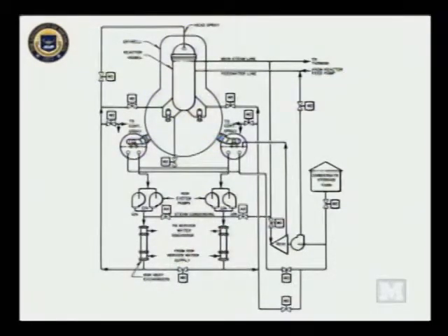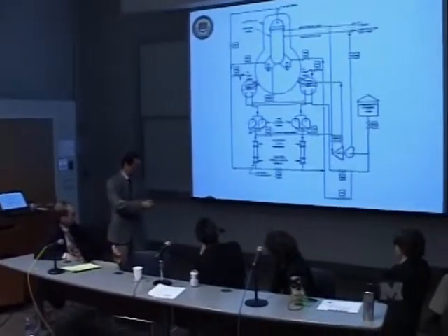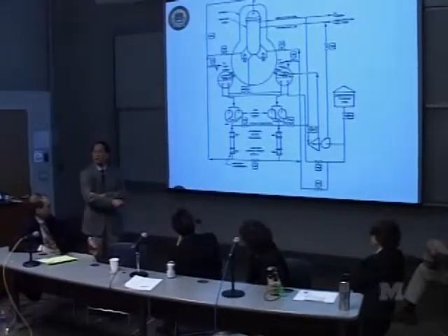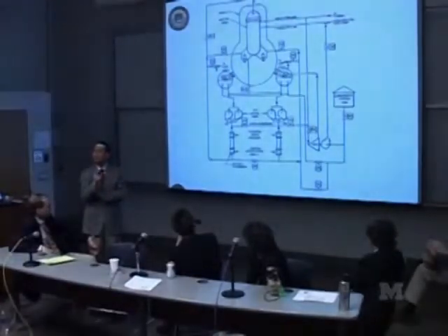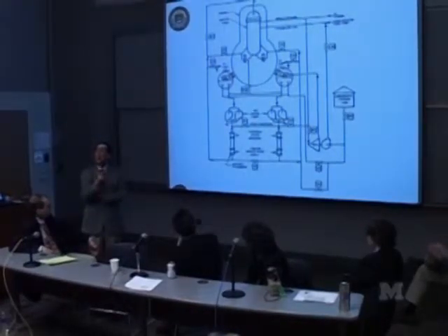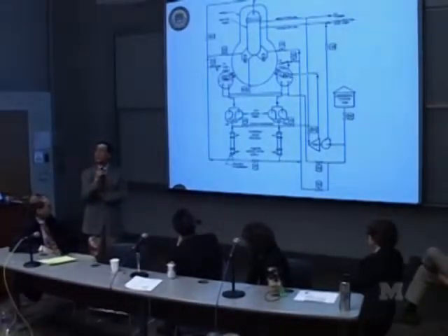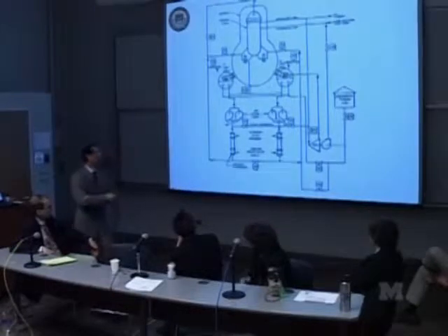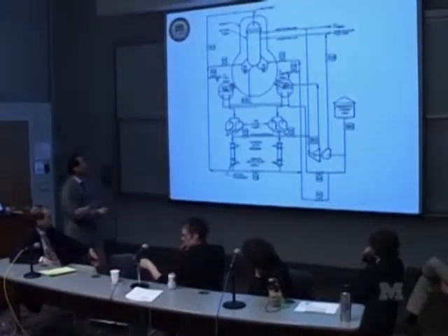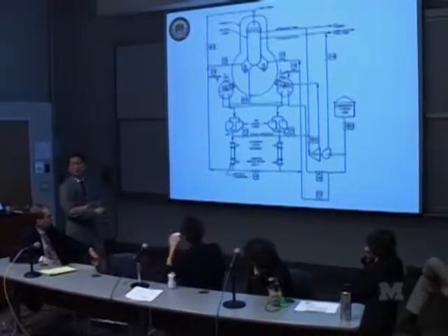But something like 12 hours after RCIC pump came on, one of the valves, I don't know which one and where, stopped functioning due to the discharge or depletion of the battery that was required to have the valve functioning. So that's when we lost the cooling capability.